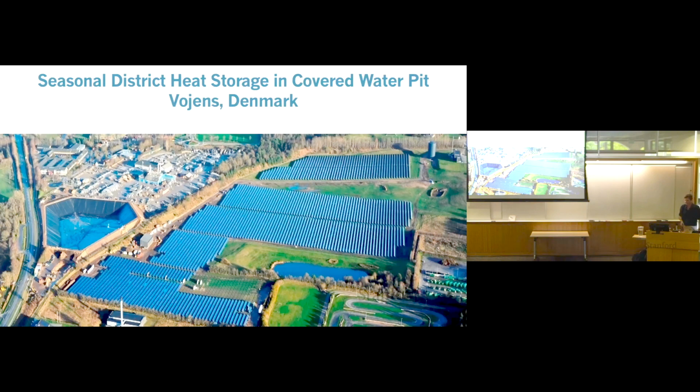Yeah, question? We are keen to ask the questions. Yeah, sure. And what's the efficiency of such storages? Well, the efficiency of the borehole storage with the soil, it's not very. It's like, I think it was like 58% from the heat collected in the summer to what gets returned in the winter. It's only 58%, but at less than $1 a kilowatt hour, it's not material.